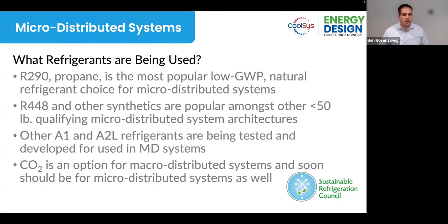So what refrigerants are being used? Propane, as I mentioned, is the most popular low GWP natural refrigerant choice for micro-distributed systems. R448, which is a very popular synthetic, but with a high GWP, is popular amongst less than 50-pound qualifying system architectures. A1 and A2L refrigerants are being tested throughout the different types of equipment ranges, and more will become available. And CO2 is a popular option for macro-distributed systems and soon will be for micro-distributed systems.